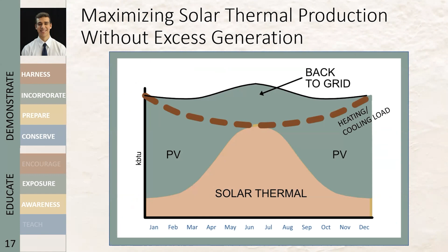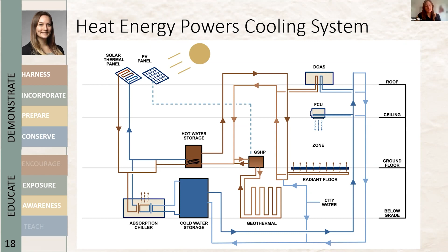To capitalize on the high generation of the solar thermal panels in summer, we paired it with an absorption chiller. The absorption chiller takes the heat generated by the solar thermal panels and uses it as a power source to make cold water, which runs to fan coil units in our building. We sized the solar thermal panels to completely cover our cooling loads.